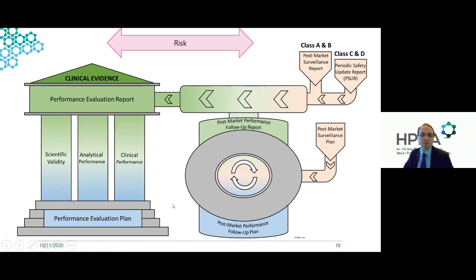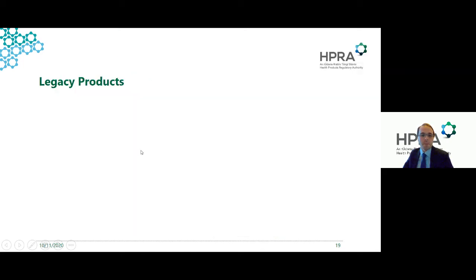But then, as part of your post-market requirements, is a post-market performance follow-up, which looks at collecting and assessing information on the performance of your device in the post-market phase. It takes input from the post-market surveillance data you're collecting anyway, and that, in conjunction with the outputs of your post-market surveillance report and periodic safety update where applicable, continuously feeds into your performance evaluation report and updates the clinical evidence over time.